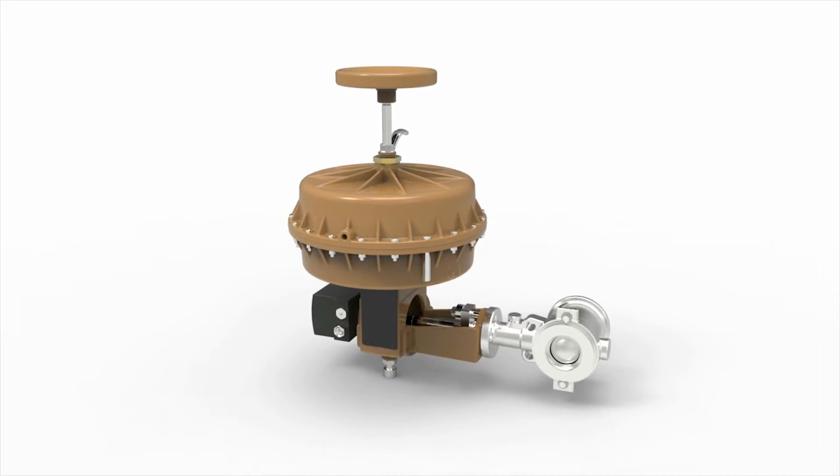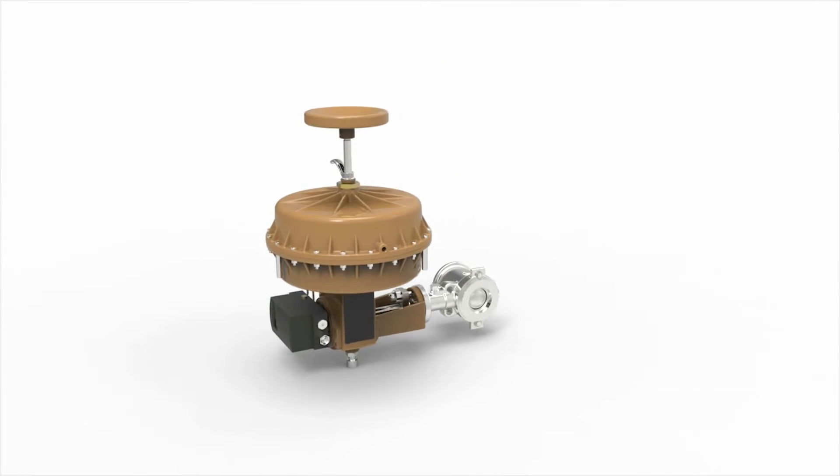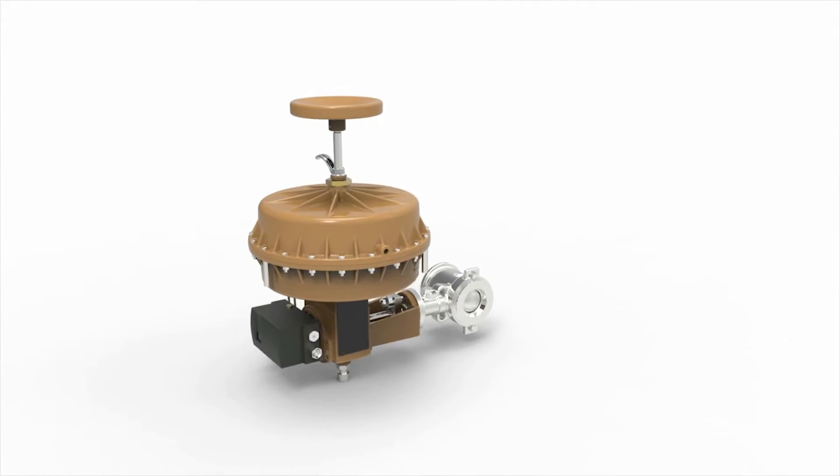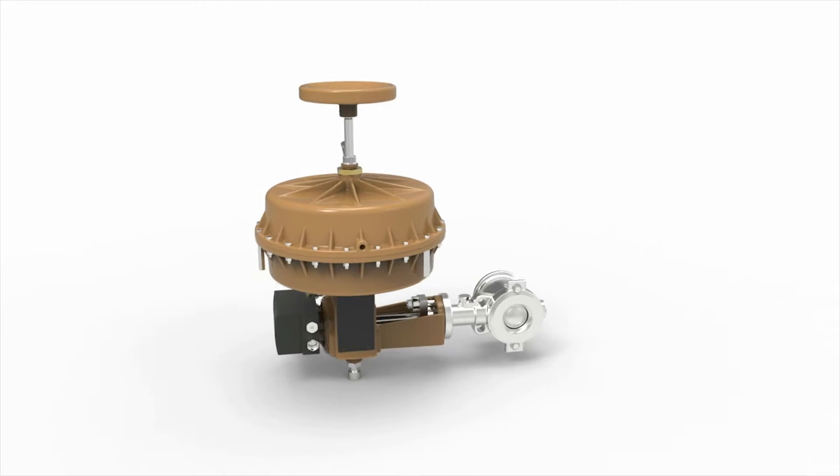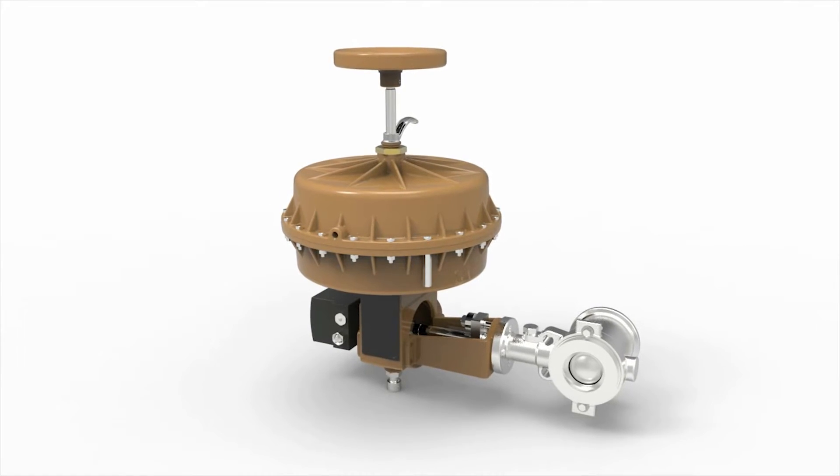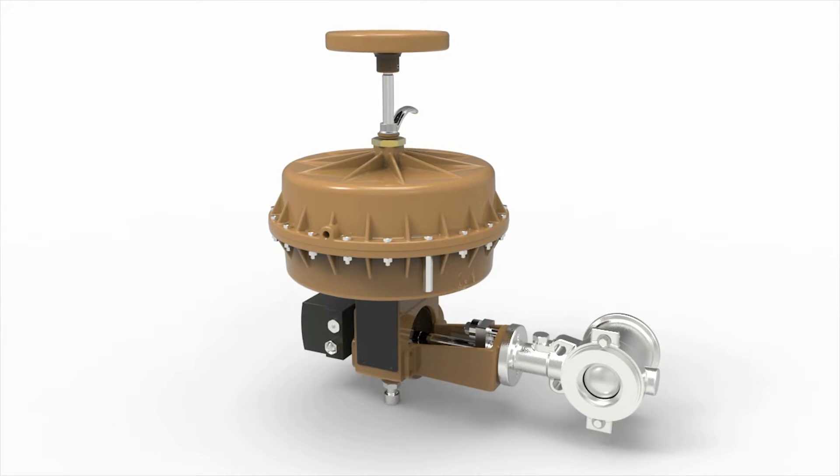The Ranger offers a selection of four body materials with a broad temperature range from negative 325 degrees Fahrenheit to 750 degrees Fahrenheit, making the Ranger adaptable for use in steam, heat transfer fluids, slurries, gases, liquids, and cryogenic applications.